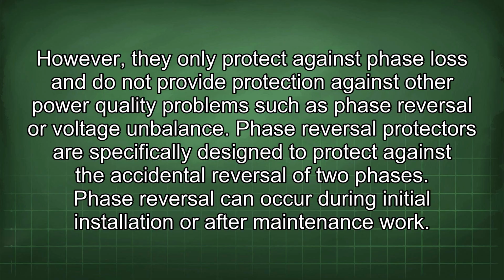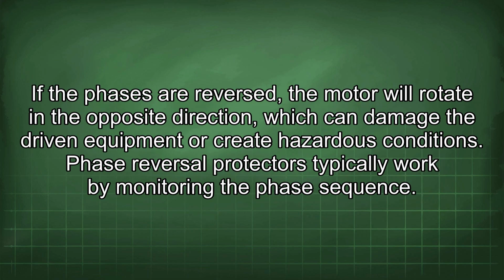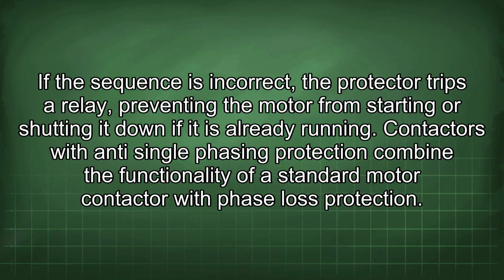reversal or voltage imbalance. Phase reversal protectors are specifically designed to protect against the accidental reversal of two phases. Phase reversal can occur during initial installation or after maintenance work. If the phases are reversed, the motor will rotate in the opposite direction, which can damage the driven equipment or create hazardous conditions. Phase reversal protectors typically work by monitoring the phase sequence.